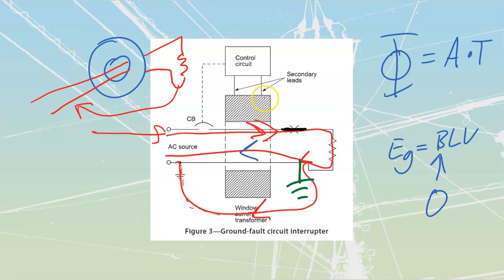All it's doing is sensing off of this. There's going to be a little tiny voltmeter inside of this circuit breaker over here that is going to read that, and then it is going to activate and kick out that circuit breaker. This is why we've got that connection to neutral that we need to have on GFCIs. Why we've got to have all of our lines going through.